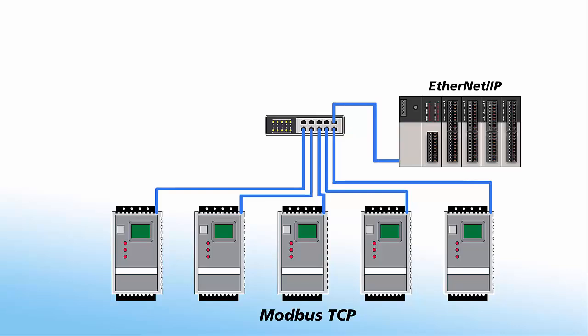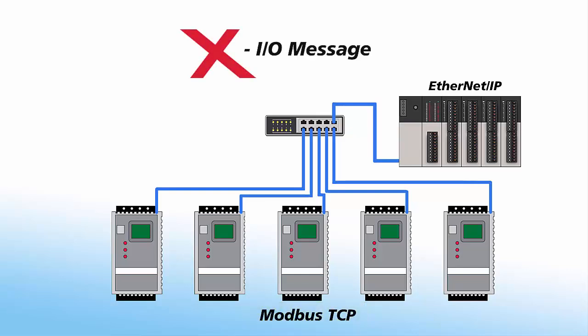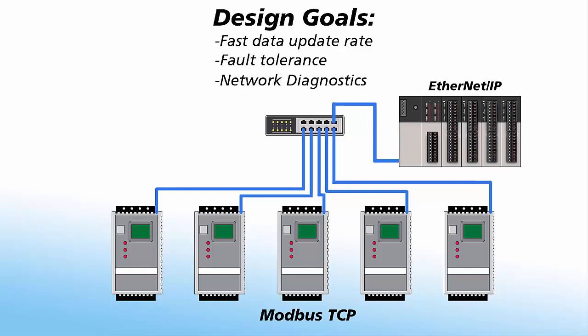For our last example, we have a PLC that needs to talk to five drives that use a different protocol than the PLC. The PLC talks EtherNet/IP and the drives talk Modbus TCP/IP. Modbus TCP/IP doesn't use I/O message communications, so we'll need to use client-server communications. The PLC will have to be a client, as the drives will be server devices. Our design goals here are high speed, fault tolerance, and communication diagnostics in the PLC. This PLC can use a message instruction and some ladder code to create Modbus TCP packets via their Ethernet communication module. Using this method has some shortcomings.